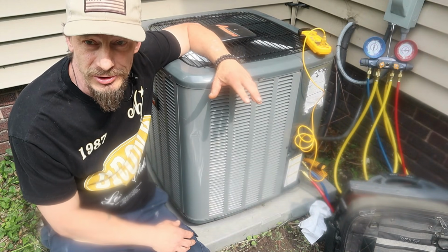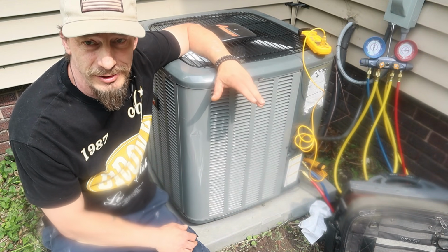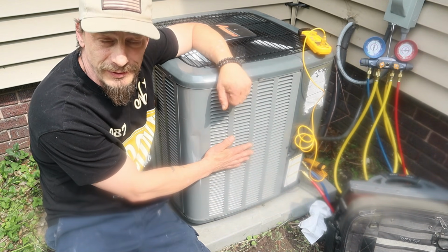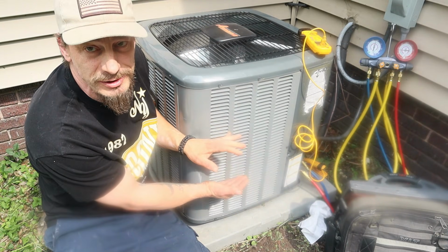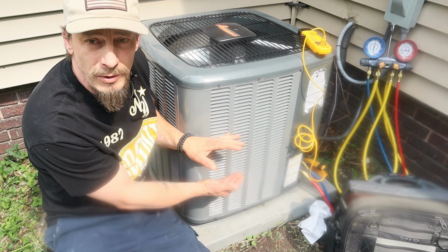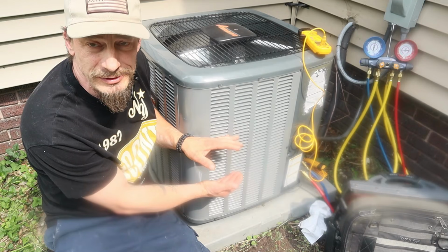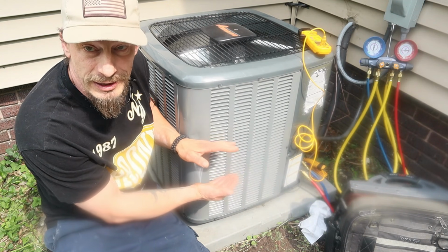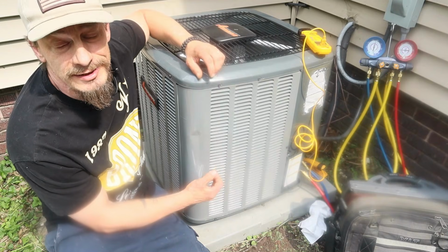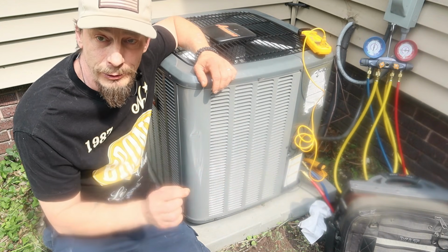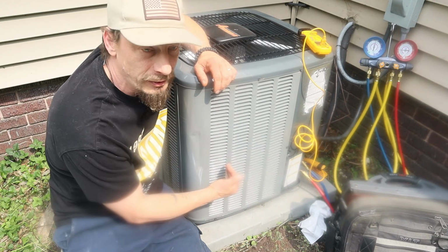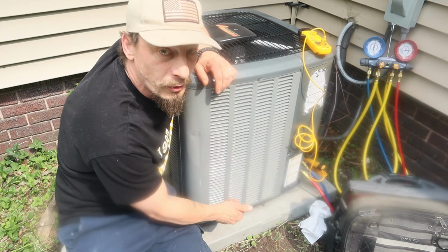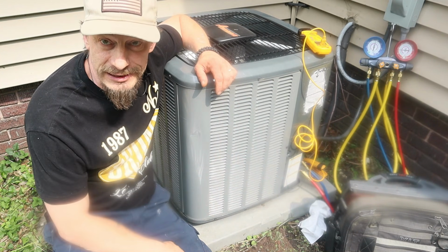Now when an air conditioning system is running properly, what's actually happening is the air is being pulled in through the sides, and there's this tight section some midway into the coil where the hot vapor refrigerant is very quickly flashing over into a liquid. And that quick transformation process creates a very solid column of liquid from that point on. So we have solid liquid throughout the remainder of the coil going all the way up to the TXV valve.